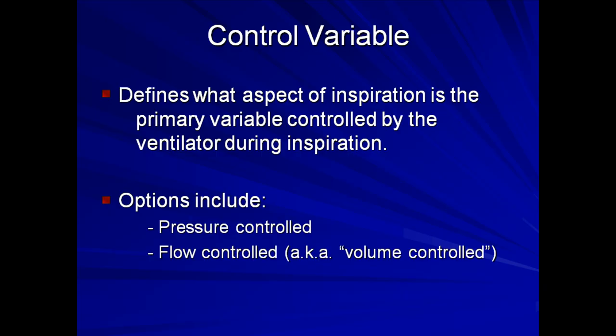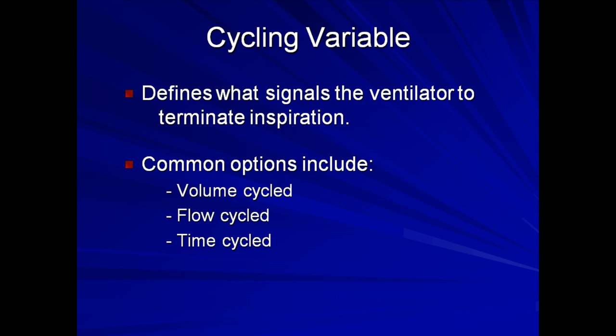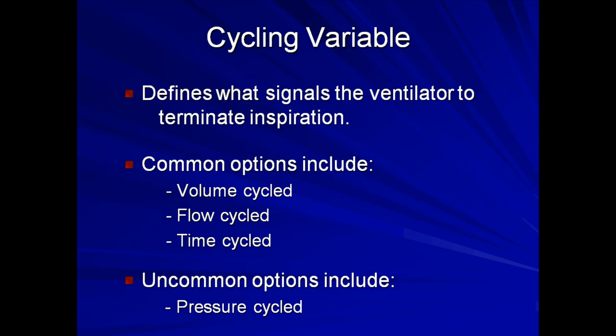The cycling variable defines what signals the ventilator to terminate inspiration. For example, with volume cycled ventilation, the ventilator will cease inspiration after a preset volume has been delivered. With flow cycled ventilation, the ventilator will cease inspiration after airflow drops below a preset threshold, typically approximately 25% peak flow. Ventilators can also be time cycled or pressure cycled. The cycling variable has some overlap with the control variable and the two are frequently used interchangeably, although some would say this is incorrect usage of the terms.